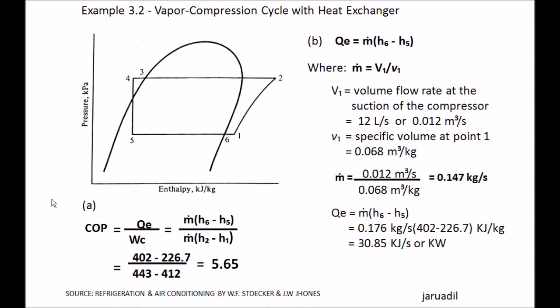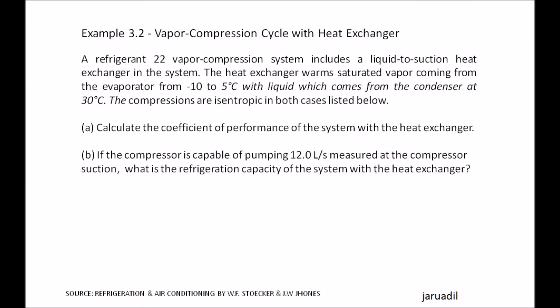Now we can solve for COP. COP equals QE over WC, which is mass flow rate times (H6 minus H5) divided by mass flow rate times (H2 minus H1). Substituting the values, the mass flow rates cancel, giving COP equals 5.65. For part B, if the compressor pumps 12 liters per second at compressor suction, what is the refrigerating capacity with the heat exchanger?